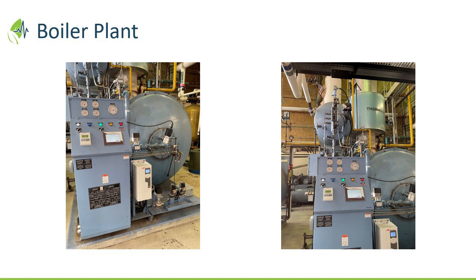Okay, so visualization, you got that massive chimney on top there. These two boilers are sitting there throughout the year. That's a big pressure trying to push air through the boilers, up out the chimney, which just takes so the boiler's working backwards, essentially. The boiler's heating the great outdoors as opposed to heating the hospital. That's actually great. We should just baseline on that. Every boiler out there these days runs at a slight negative. So when all these stacks and chimneys were put in place, regardless of your boiler type, they are designed to have a slight negative on the stack in the worst case scenario, typically summer, right? Because you don't have enough draft.